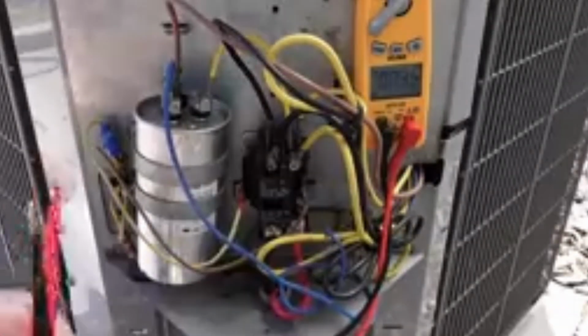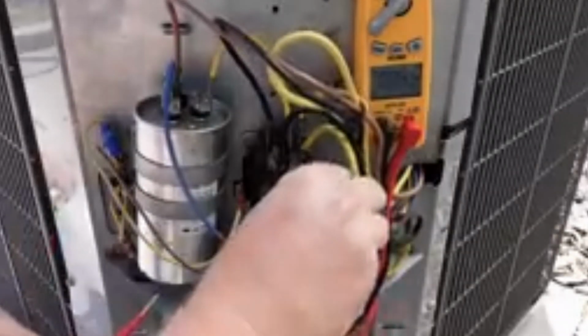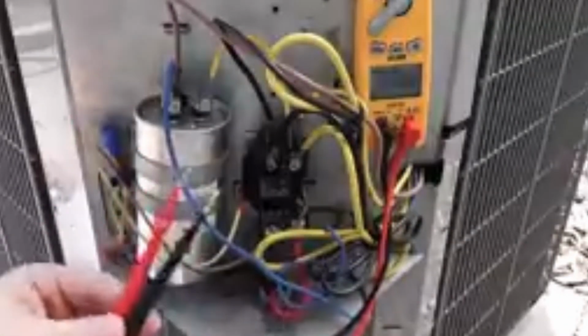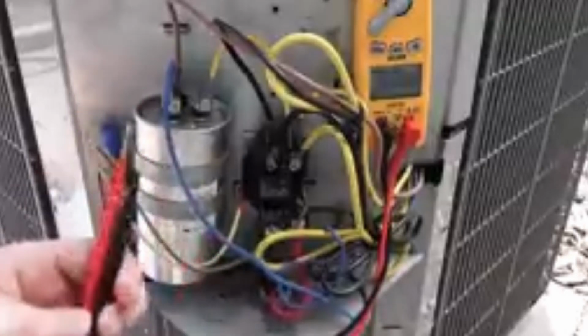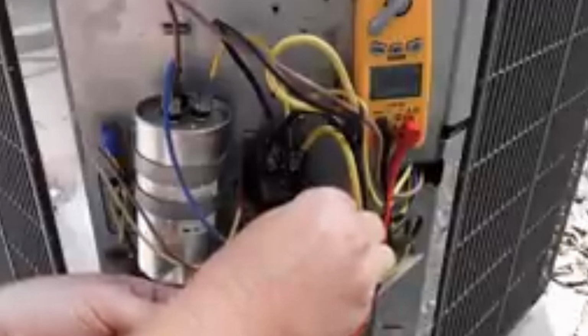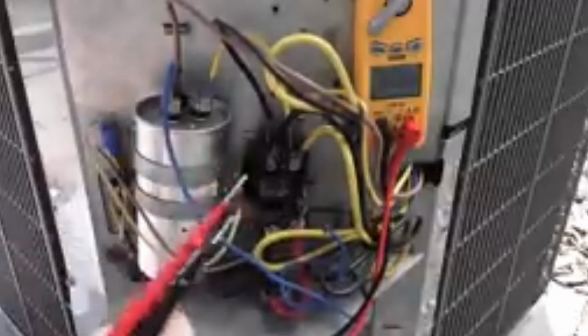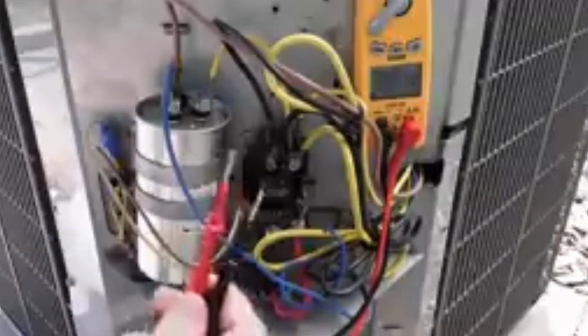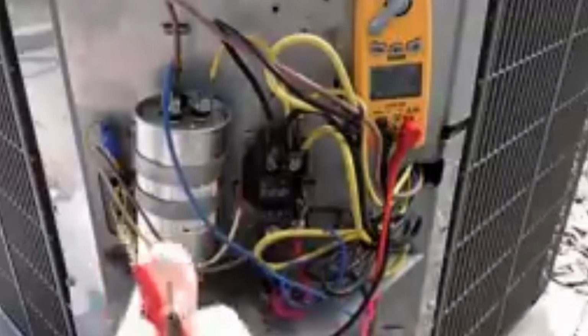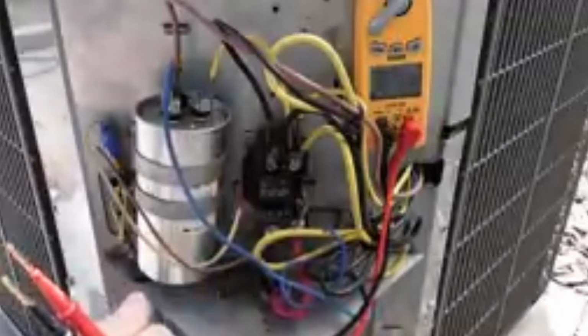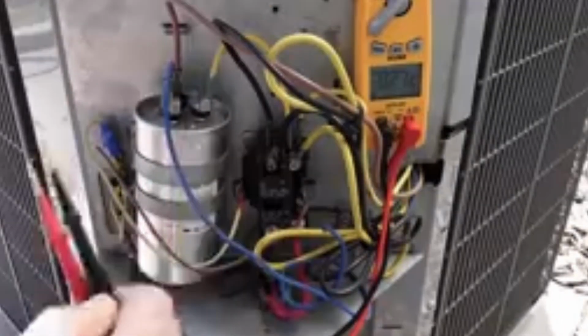I only use measurements from hot to ground for a safety test. I don't use them for diagnostic purposes. This is because these measurements can give you a false reading when you have a backfeed situation, such as in the case of when a disconnect or breaker only has one leg connecting. So safety to ground, yes. For diagnostic purposes, generally not, unless you're doing an ohm test to ground.